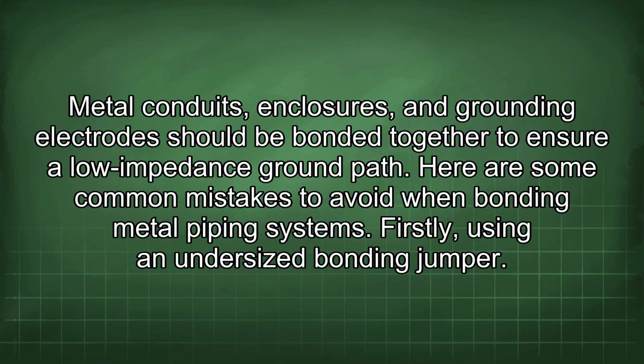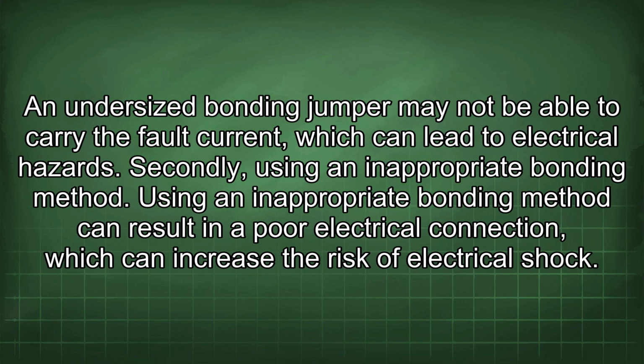Here are some common mistakes to avoid when bonding metal piping systems. Firstly, using an undersized bonding jumper. An undersized bonding jumper may not be able to carry the fault current, which can lead to electrical hazards. Secondly, using an inappropriate bonding method. Using an inappropriate bonding method can result in a poor electrical connection, which can increase the risk of electrical shock.